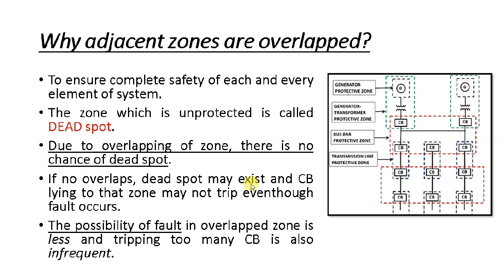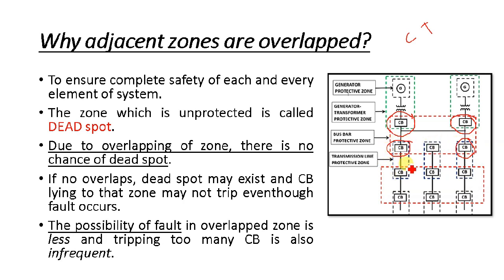Now let us understand this diagram. The boundary of the protection scheme — for the generator and transformer protective zone, for the generator, for the bus bar, and for the transmission line — these boundaries are decided by the location of the current transformer (CT). You can see that many protective zones overlap. The bus bar protection zone and the generator-transformer protection zone overlap in certain parts. So what is the need for overlapping? Why do we go for the overlapping of protection zones?